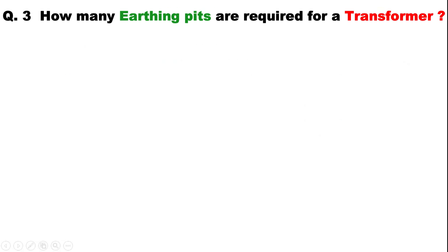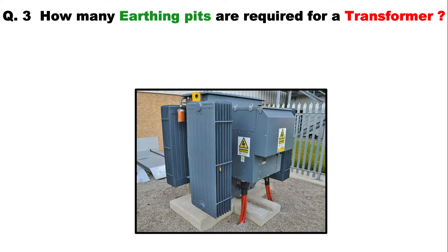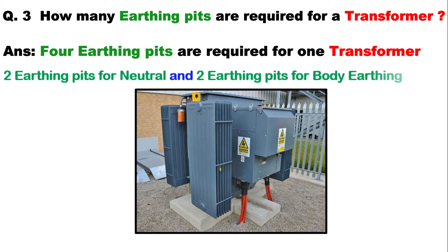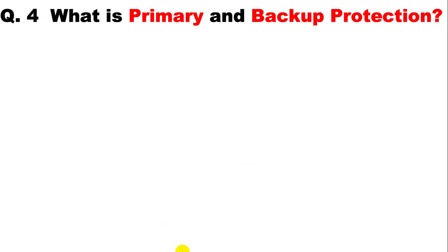This question can also be asked in a different manner: for a distribution transformer, how many earthing pits are required? The answer is the same — for a distribution transformer also, four earthing pits are required: two earthing pits for neutral and two earthing pits for body earthing.